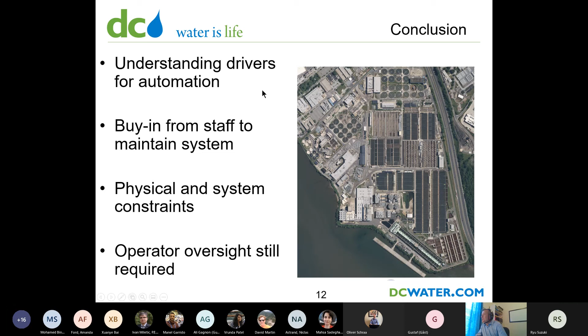Anna Pena from Fort Worth is asking why the blowers were more efficient in 2016. In 2016? Oh man, I'm glad you asked that. It's because that was the time when we were actually using more air. Remember, for these blowers, it's the apparent efficiency, how much power the blower draws per airflow. The more you push the blowers, the better efficiency you get. Okay, so that's the efficiency curve of the blowers, and the air consumption was more favorable for the curve. Yep, exactly. Good.